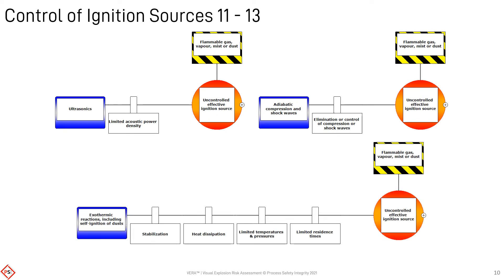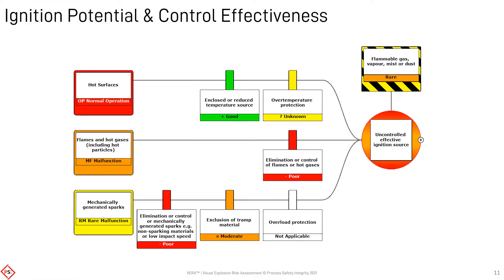Sensitive materials, which have the potential to auto-ignite, should be stored or processed under benign conditions. The likelihood of an ignition source occurring or being present can be categorized using a simple relative frequency ranking, according to the conditions that would create the threat. The effectiveness of each prevention control can also be relatively ranked, based on evidence, experience, or judgment.